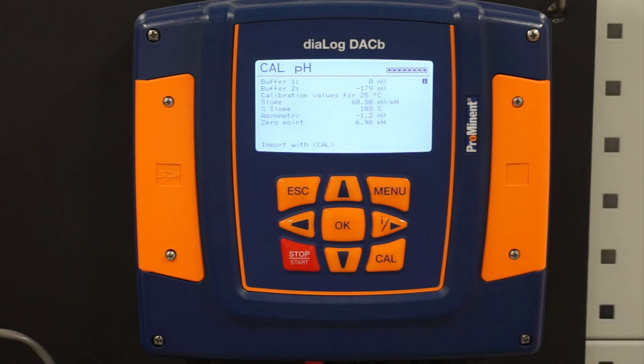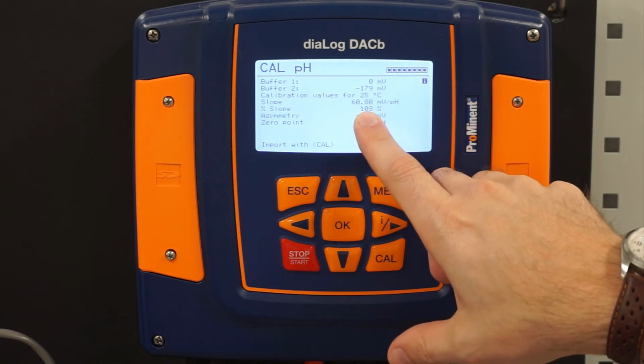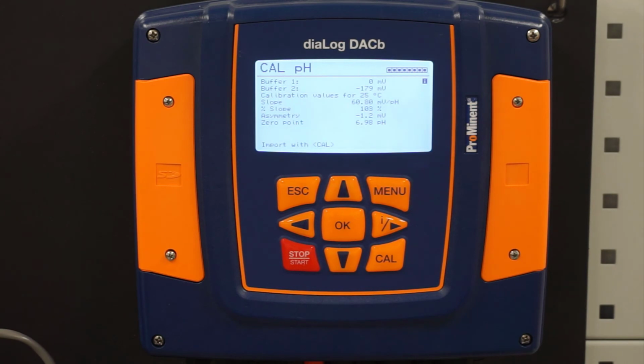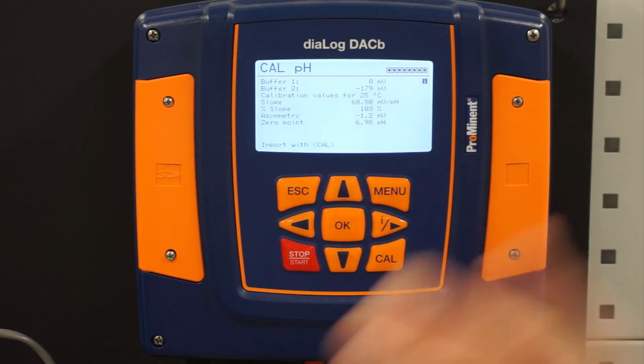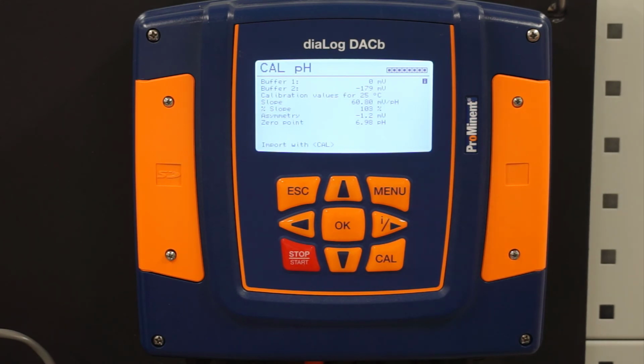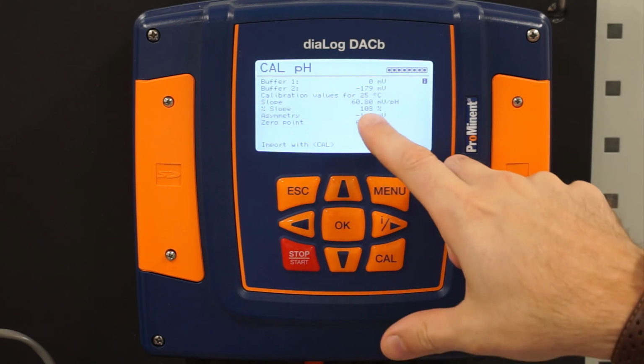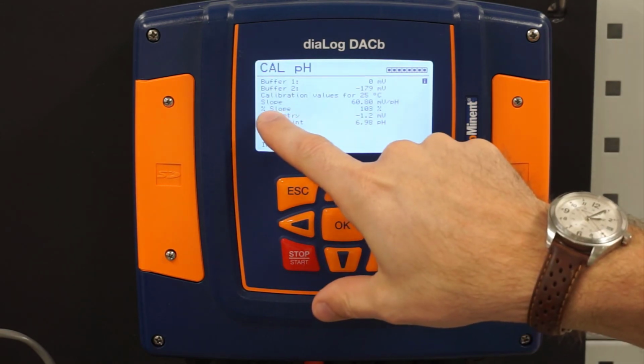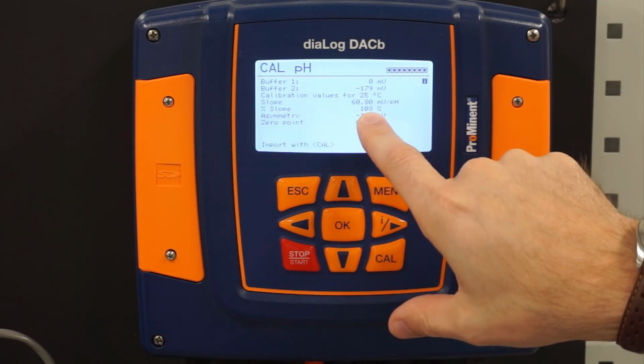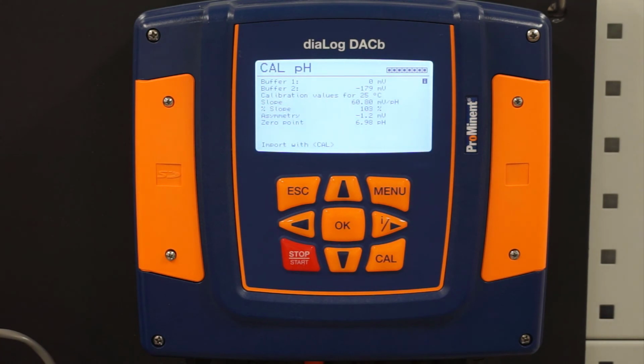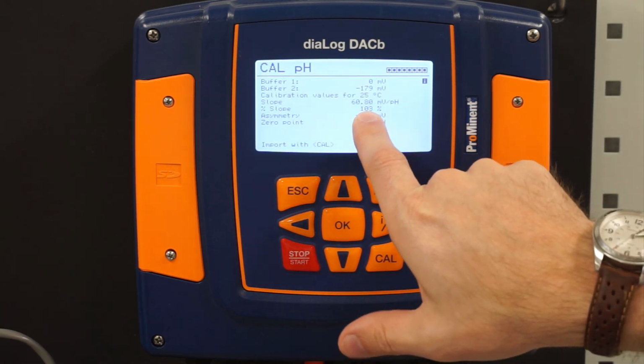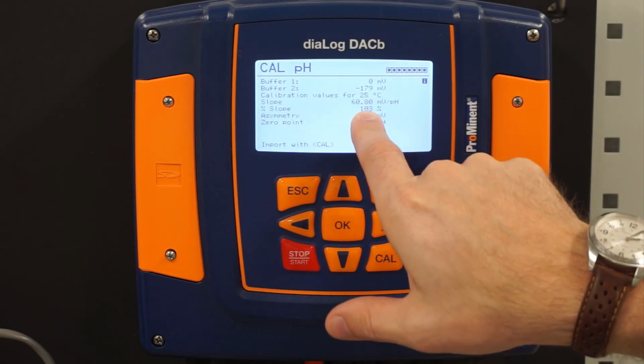So as we're doing calibrations, this number is gradually going to drop as the electrolyte, the gel inside the pH sensor, wears out. That number is going to start dropping. It will allow us to do a slope calibration until we get down to 20%. Once we get to 20% or below, we're going to get a calibration error, and it won't allow us to calibrate below that.